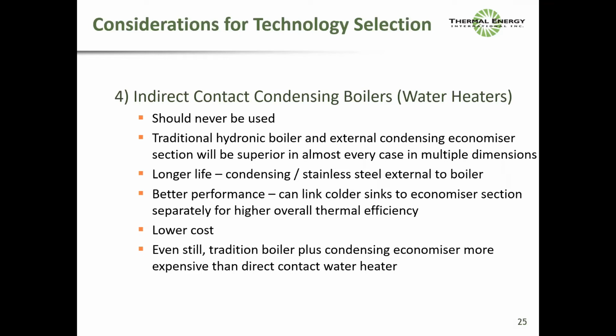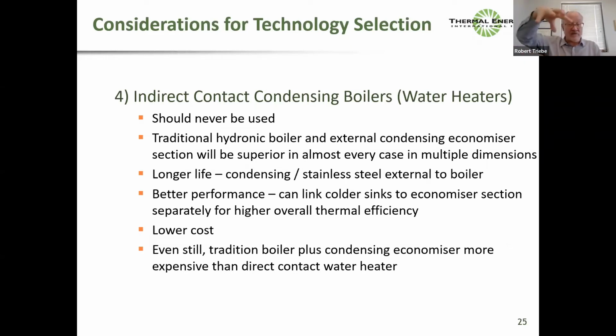Okay, and somebody's asking how much water is consumed during operation of these boilers. No water is consumed. Water is produced. We are condensing water from the flue gas. We are making water from the flue gas. And the beauty of that is it creates a continuous blowdown without ever adding water. Because we're cooling the flue gas to below its dew point, we're creating water, which at our food and beverage facilities, we return to their cooling tower systems and reuse, and although it's not worth a lot of money, we're able to claim huge water savings as well.